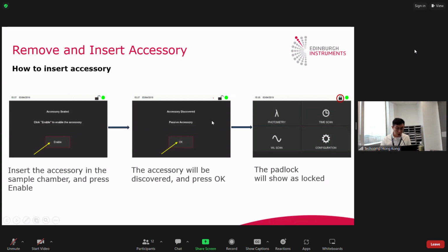After you change to the proper sample holders, you can insert the sample holder into the sample compartment, and then you can see a screen like this one. You can press enable, and the instrument will automatically discover that there is an accessory connected to the instrument. Then you can press OK here, and the padlocks will be locked, and you can use these sample holders to do the measurement.